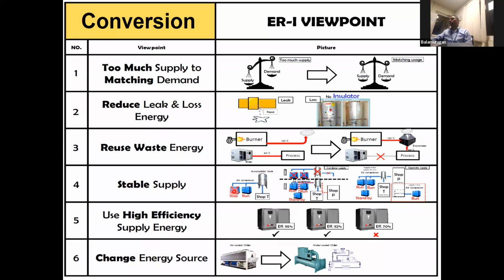Stable supply - for example, we have one machine running and one stopped, with an accumulator or receiver tank for an air compressor, and say 3 more equipment running with 2 stopped for a shop. How do we optimize this, running 4 as 3, and use it for the process, even having a small baby air compressor for smaller applications at the end area. This is how we need to optimize stable supply.